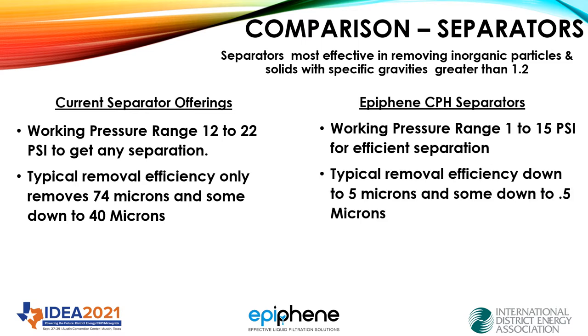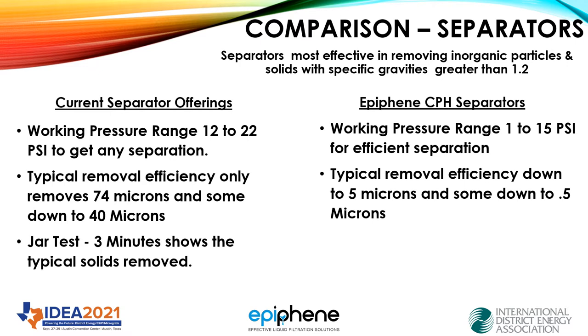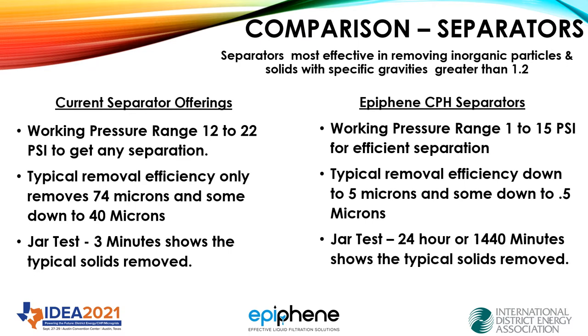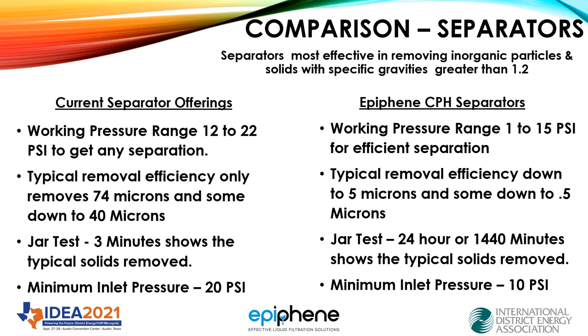Typical removal efficiency for the CPH is 5 microns, and we get up to 33% of the half micron. The jar test is an industry standard to show what effect a separator would have on a level of solids, and 3 minutes settling time is usually what's used for current offerings, whereas we use a 24-hour test — or 1,440 minutes — to show what could be removed. Minimum inlet pressure is 20 psi for most of those separators; our minimum inlet pressure is 10 psi.